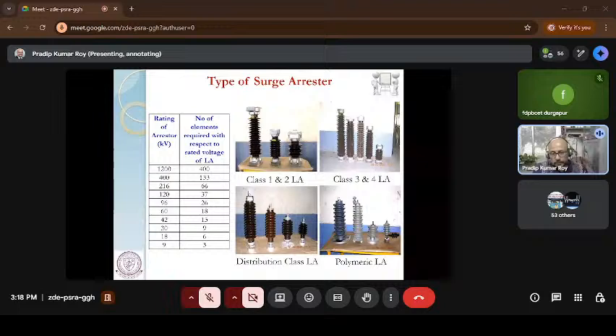Now this figure, if we look at the bigger one, it is actually only 400. Now I am talking about a 1200 kV surge arrestor, so the height is almost 3 times, and this, as I said, is normally outdoor equipment. It is installed outside, mostly in outdoor applications. Now there is a test called the seismic test. In the seismic test, the ceramic porcelain cannot survive because ceramic doesn't have any kind of plasticity. It's a brittle material, so it will immediately crack.